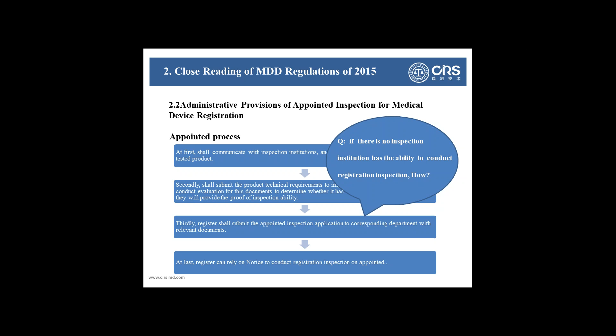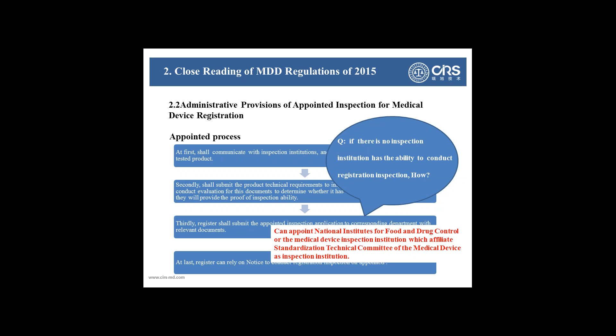Here's a very interesting question. What if there is no inspection center that has the ability to conduct the registration inspection? In China, there are a total of 26 testing centers now, and they are qualified to provide the testing service. So, if your product cannot be tested by these 26 testing centers, what do you have to do? The answer is you can appoint the National Institutes for Food and Drug Control or the Medical Device Inspection Institution affiliated with the Standardization Technical Committee of the Medical Device. So you can find this organization to help do the testing.